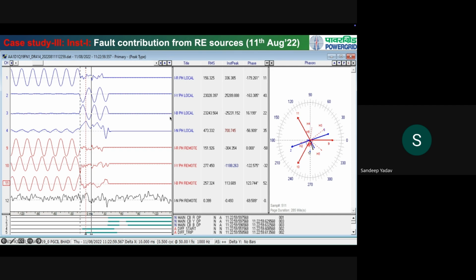So from the grid side, Y and B phases, they feed 23 kiloampere in phase opposition. However, from the solar plant side, the contribution is largely positive sequence and not more than the rated current of the inverters. So this is the difference. So these currents have large negative sequence, because this is a phase-to-phase fault, you will have a large negative sequence. However, on the solar plant side, in case of a phase-to-phase fault, we only have positive sequence contribution, right?